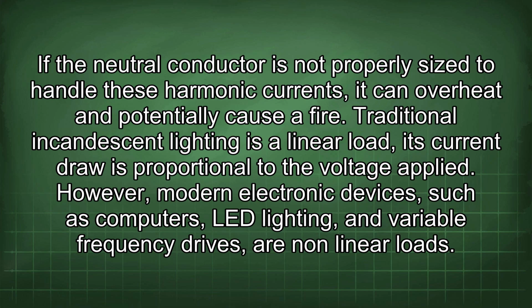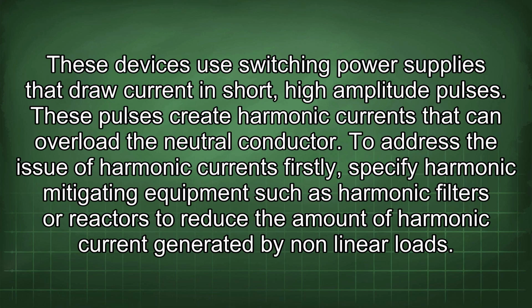Traditional incandescent lighting is a linear load. Its current draw is proportional to the voltage applied. However, modern electronic devices such as computers, LED lighting, and variable frequency drives are nonlinear loads. These devices use switching power supplies that draw current in short, high-amplitude pulses. These pulses create harmonic currents that can overload the neutral conductor.